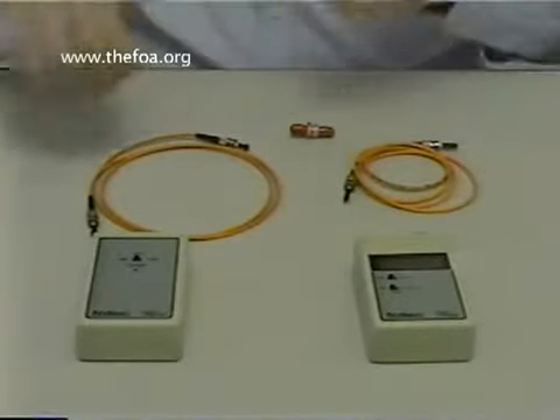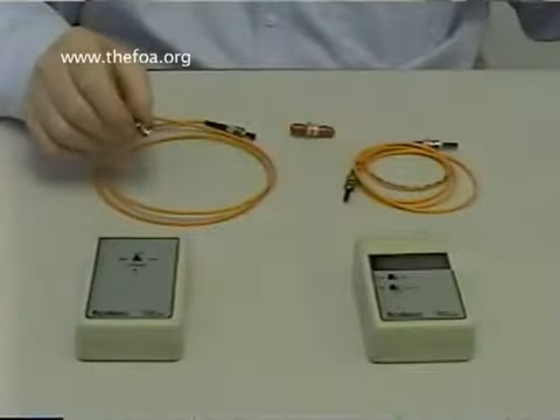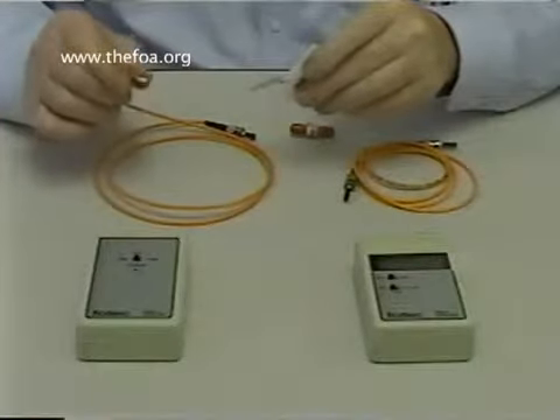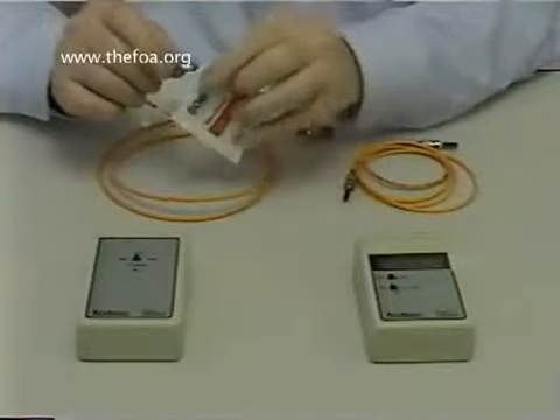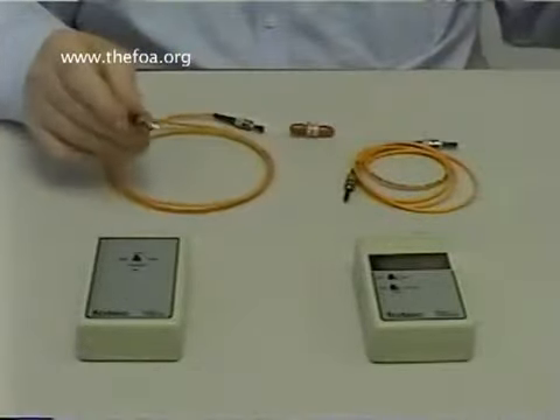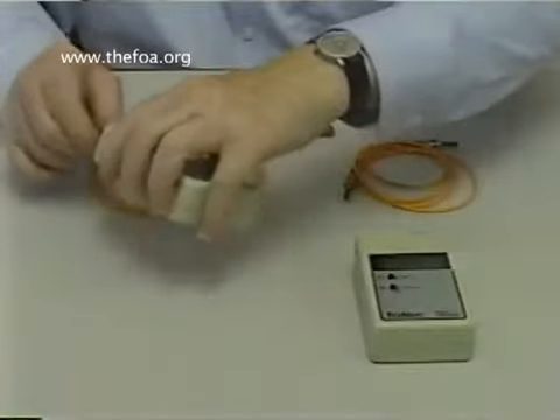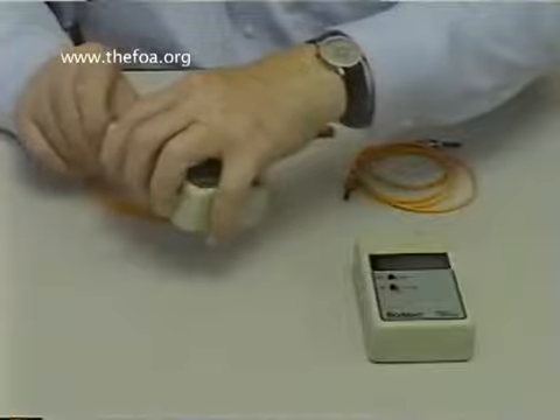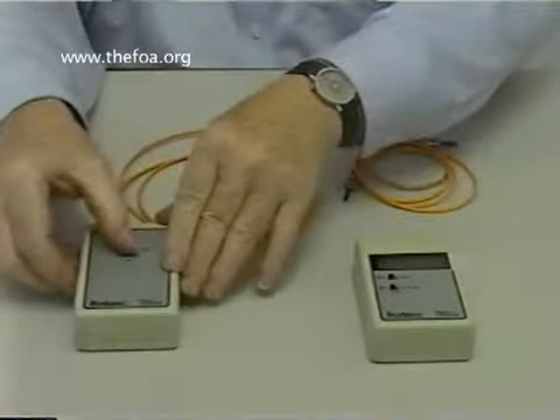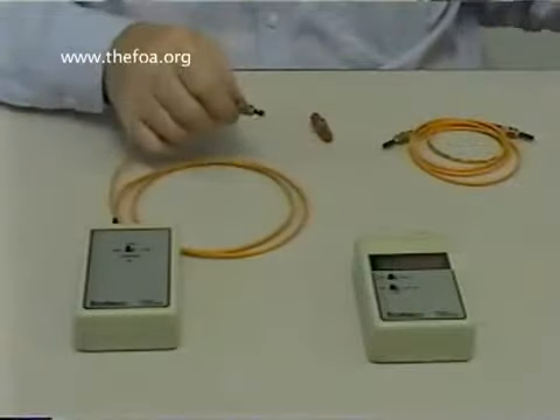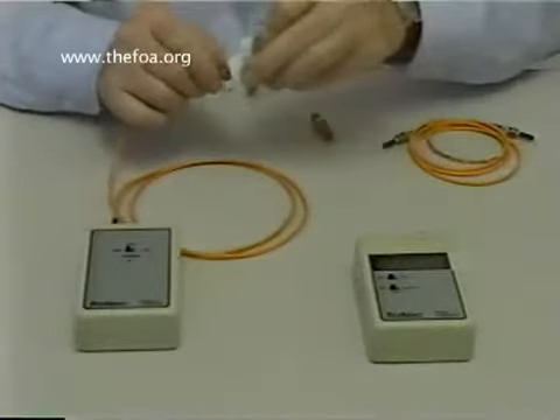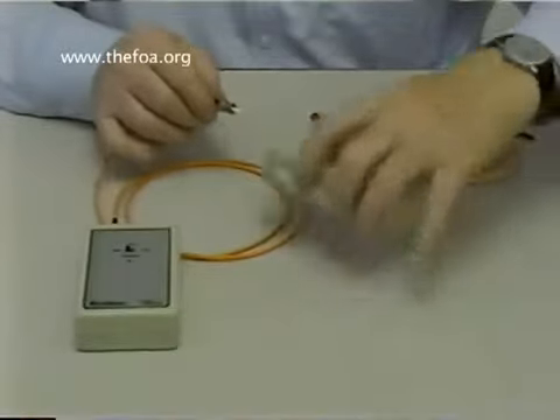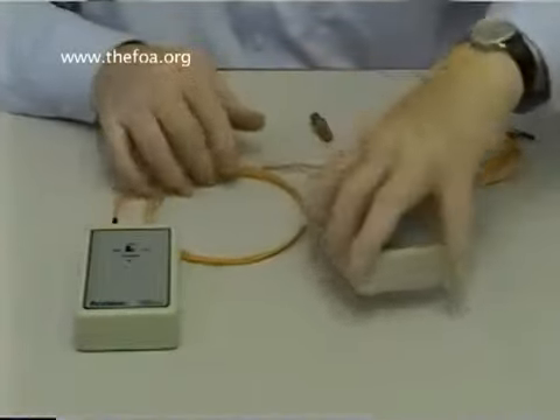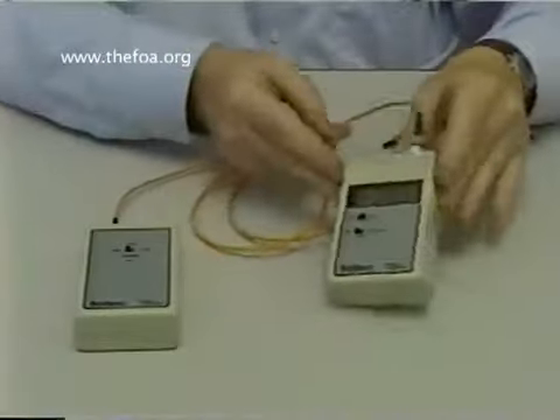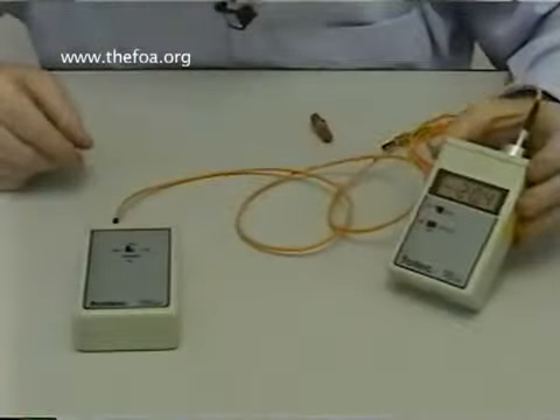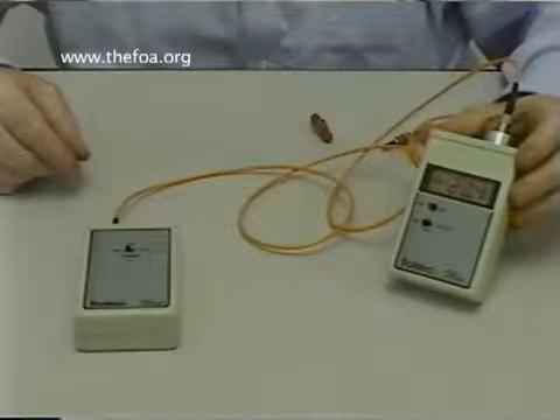The first thing we're going to do is to take the dust cap off our cable. We always keep the dust caps on our connectors except when we're using them. I'm then going to use an alcohol pad and clean the end of the connector to get any dirt off it and attach it to the 850 nanometer output of my source. I'll turn on my source, take the other end of my cable, remove the dust cap, clean it, attach it to my meter, turn on my meter, and read the output. The output is minus 20.4 dBm.